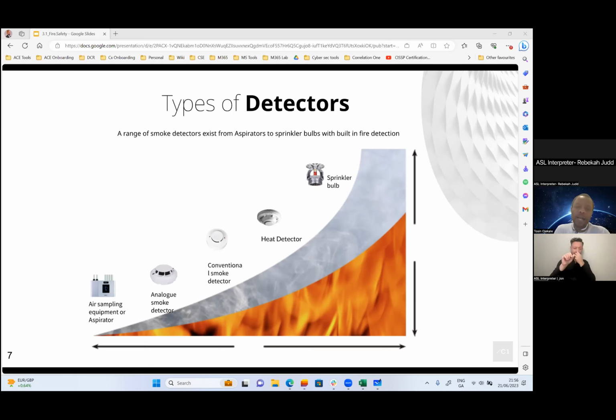Some spaces will require you to have just heat detector and sprinkler bulb. Some spaces, like maybe the office spaces where people are sitting, you are likely to have just conventional smoke detector and maybe sprinkler bulb in most of those cases. So it depends on the environment. Most times you will have a combination of the two. But what I've seen in most gray areas, you will just have every other thing apart from the sprinkler bulb, because of the other elements that are available there. So you might not want to use sprinkler bulb there.